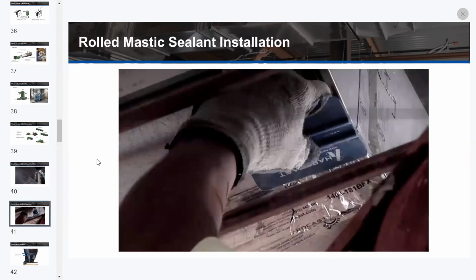When we're talking about a spray applied, that takes a lot of that out. What you'll find on a spray applied is you're spraying, typically with an airless paint sprayer that's slightly modified to spray a duct sealant. And you're spraying at a pressure of 15 to 1800 PSI. At that pressure, when you're going into that joint or seam, you're actually driving that sealant into that joint or seam at high pressure. So if you're talking about spray applied, you'll get a better seal than typically you will with a bucket and brush.